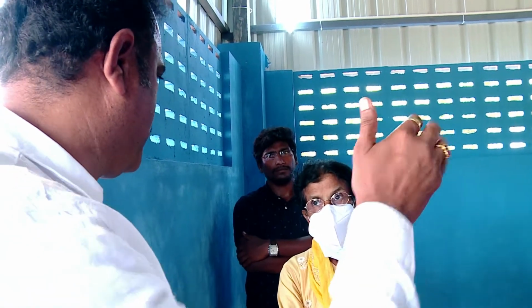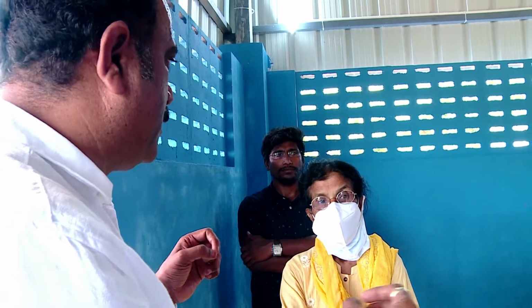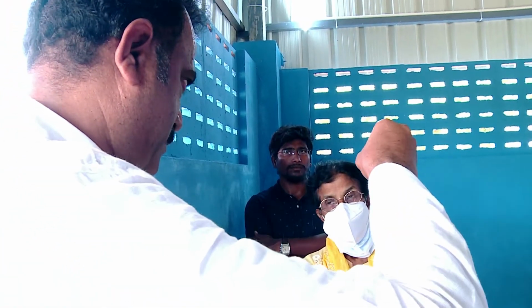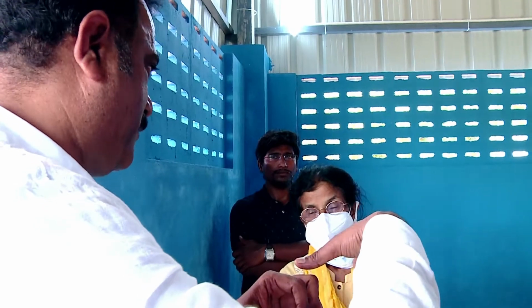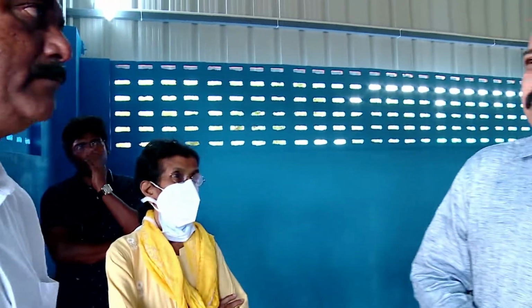If there is any possibility of dioxin and furan formation, we put a secondary heater on the outside of the chamber with a residence time of 2 minutes, where all the dioxin will again be destroyed into carbon dioxide and water. It then goes to the spray tower as a wet scrubber, which removes all the acidic fumes, and only pure air goes out.